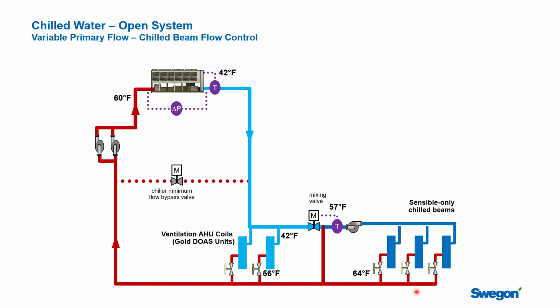The control for the secondary loop that goes to the chilled beams, in this case, we're using a temperature sensor on the supply water to the chilled beams, and it's modulating how much chilled 42 degree water is being introduced to this loop to cool it down to 57. So typically the return water temperature on chilled beams is about 64, 65 degrees, somewhere in that range. And so that water comes back, we mix it with some 42 degree water to deliver 57 degree water to the space. If this was a heat exchanger application, you'd still have a supply water temperature sensor, but it would be modulating the flow through the heat exchanger to deliver the right temperature to the space.